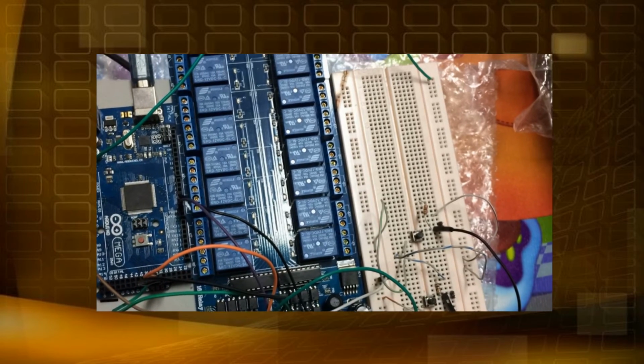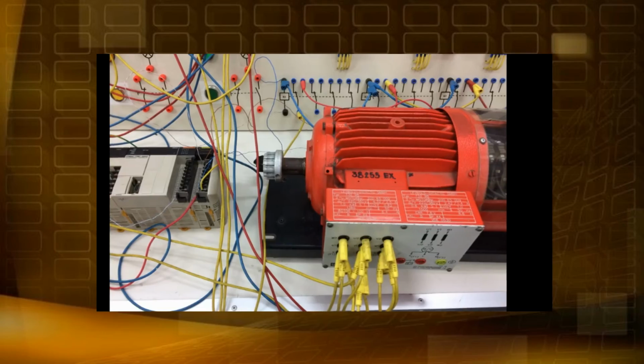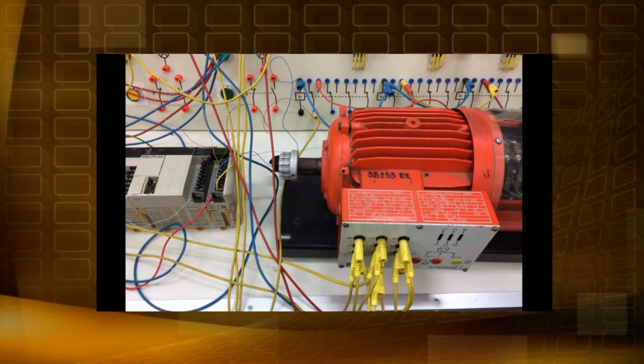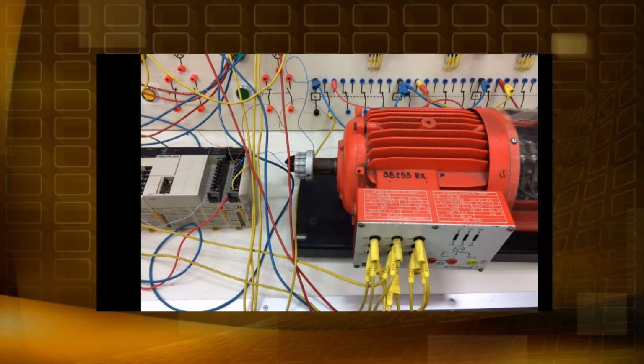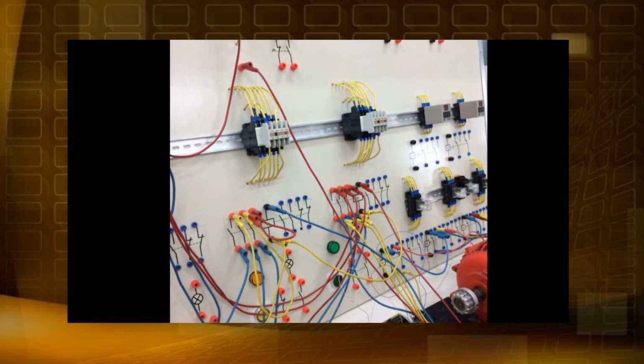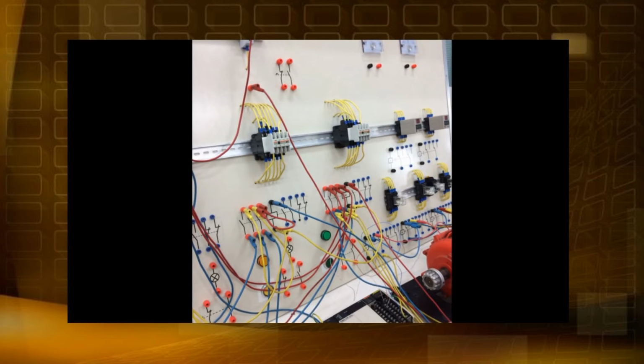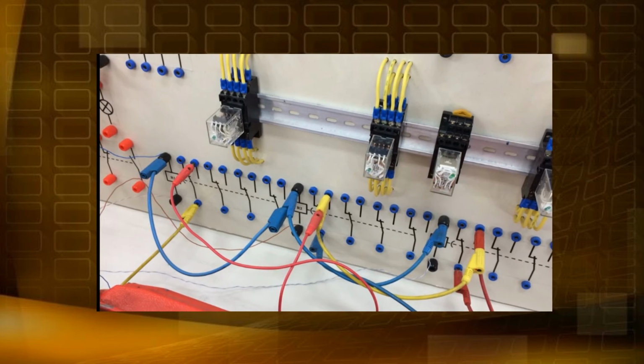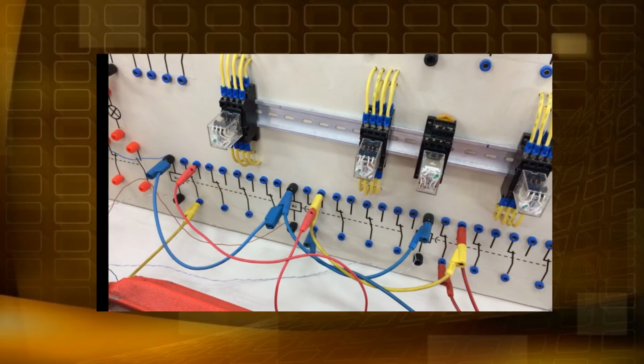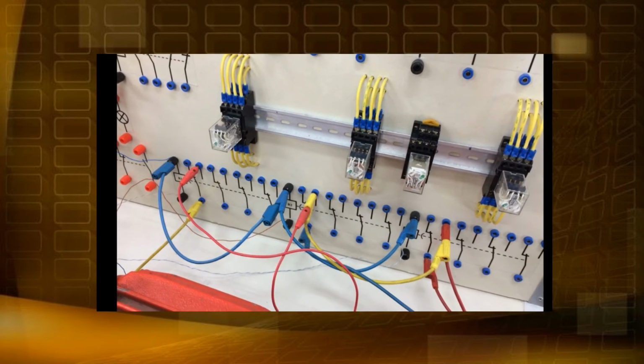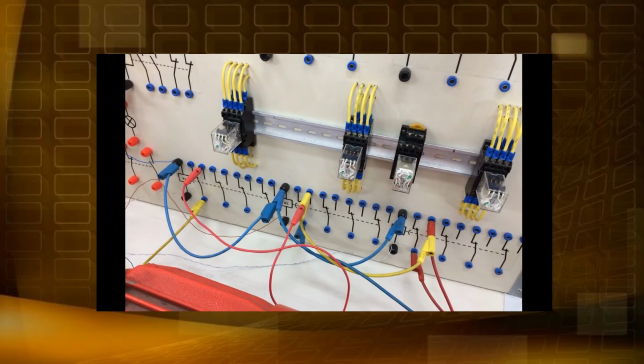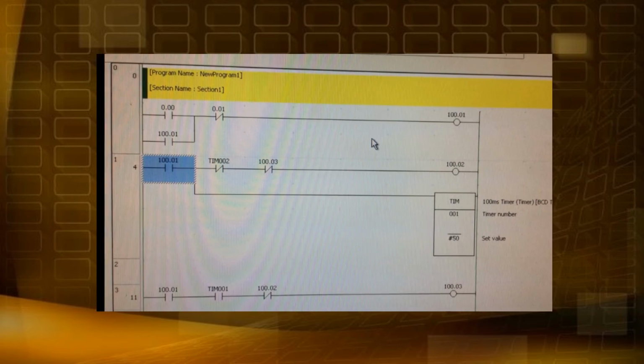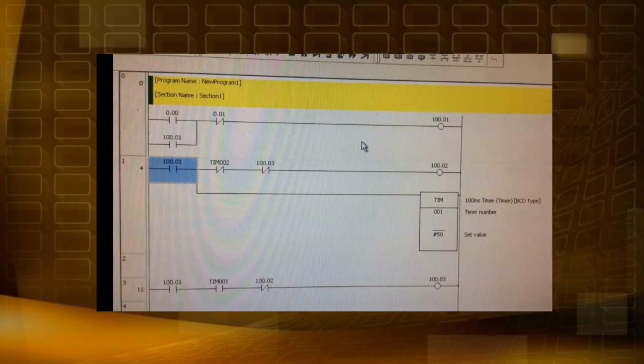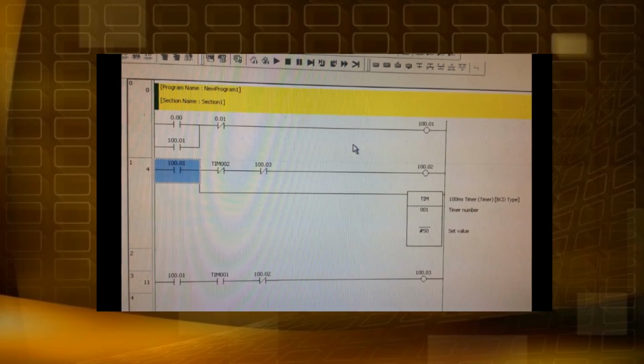Voltage reduction during star delta starting is achieved by physically reconfiguring the motor windings. During starting, the motor windings are connected in the star configuration and this reduces the voltage across each winding. After a period of time, the windings are reconfigured as delta and the motor runs normally. They are used in an attempt to reduce the starting current applied to the motor during starting, as a means of reducing the disturbances and interference on the electrical supply.